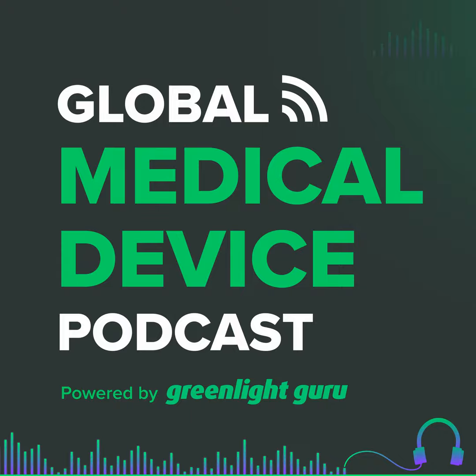Would we need an IRB approval for a device that's already on the market to do a clinical trial for an indication that is not currently on the FDA cleared or approved label? That's clearly in the gray area. The regulation does not say one way or the other. In that particular case, I revert to institutional policy.